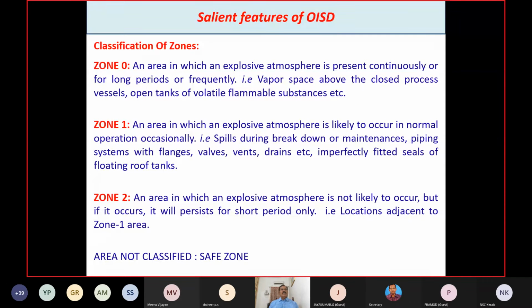The zones are classified as zone 0, zone 1, zone 2. Zone 0 means an area in which an explosive atmosphere is present continuously, for a long period, or frequently. For example, the vapor space above closed process vessels or open tanks of volatile flammable substances. There the explosive atmosphere will always be present continuously.